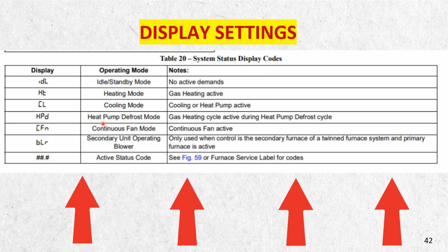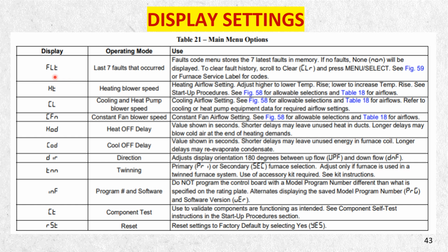All right, so here's what your display settings will look like. When it's not getting a call, you're going to have an IDL, or idle. The HT is your heating mode. The CL is your cooling mode, and then you're going to have your heat pump defrost mode on some models. Some models don't have it. Continuous fan is the CFN, and then you'll have your blower, secondary unit operating blower, and you'll have some codes there. This is usually the one I'm taking out. This is what you see. There's the fault, with the last 7 faults, how to get into the fault code, how to clear it.